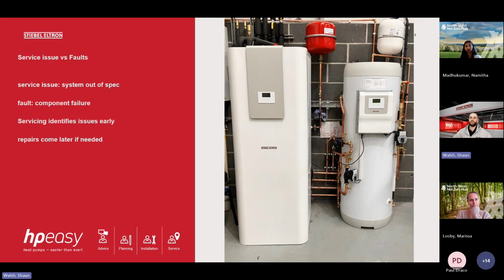Okay. With failed components, generally that means the system can't operate at all, and you'll typically know about that long before you have to go for a service. If it's a failed component, it would generally be a call out and an emergency, because the machine actually wouldn't be working at all. But when we do servicing, we protect all of these components from future failing. Like I say, if we have pumps and expansion vessels, when we're checking all these regularly, we avoid future failures with these components. Okay.